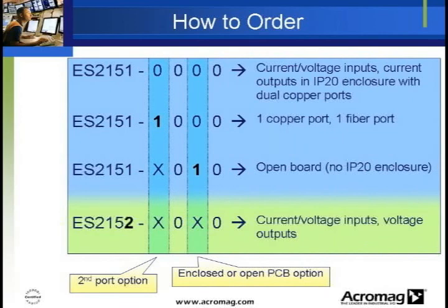The EtherStax modules may be ordered in different configurations. While both the ES2151 and ES2152 feature analog current and voltage inputs, the ES2151 is the analog current output model, and the 2152 is the voltage output model that comes with a DB25 connector on the voltage outputs for optional connection to an isolated amplifier module. The EtherStax units may also be ordered with either dual copper ports or one copper and one fiber optic port. Each of these configurations are available either as an enclosed module or as an open PCB board for custom applications.